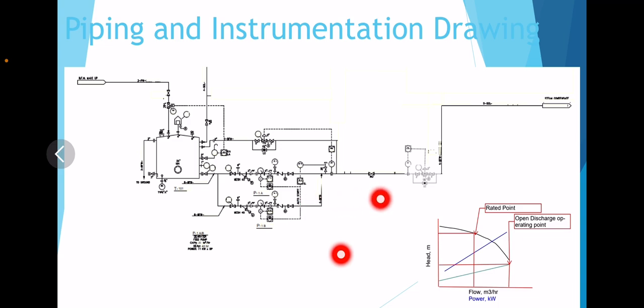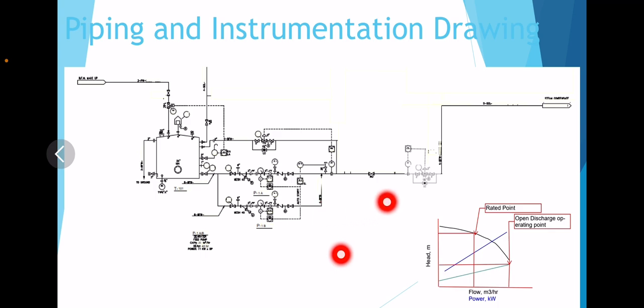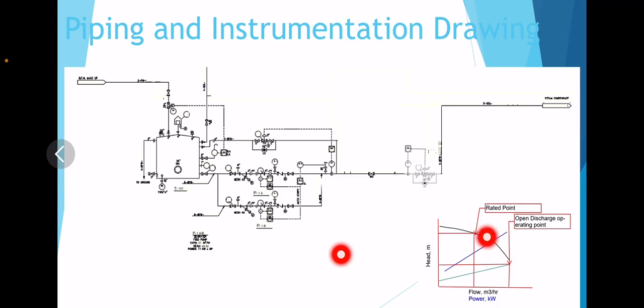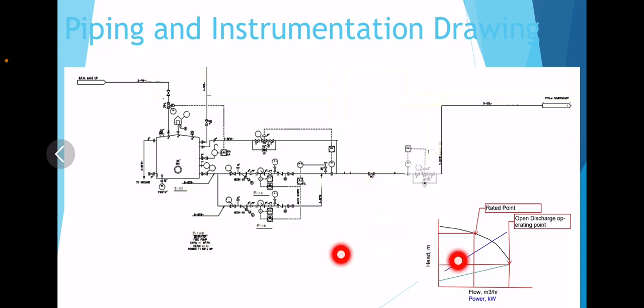But before the spare pump starts, the forward flow control valve tends to go open to satisfy the flow requirement. So when the second pump starts, the control valve is fully open — meaning the pump starts under a full-open discharge condition. Looking at the pump performance curve, the normal rated point is up the curve where the power required is lower, and the end-of-curve power requirements are higher. Therefore, best practice is to ensure that pumps designed for auto-start have their motors designed for end-of-curve power requirements. Thank you.